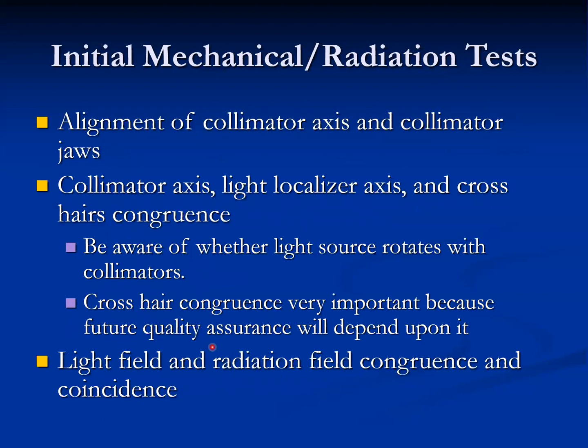Initial mechanical radiation tests include alignment of the collimator axis and collimator jaws, collimator axis, light localizer axis, and crosshair congruence. Be aware of whether the light source rotates with the collimator. Crosshair congruence is important because future quality assurance will depend upon it.